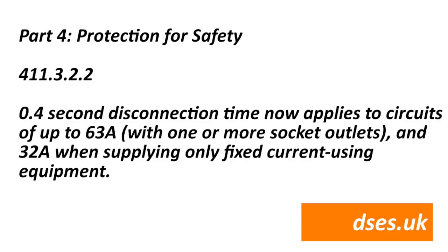Regulation 411.3.2.2 previously stated the maximum disconnection time for TN installations of up to 230V AC was 0.4 seconds for any circuit up to 32 amps, and 5 seconds for higher-rated distribution circuits. That has now changed slightly: 0.4 seconds now applies on circuits up to 63 amps with one or more socket outlets, and still 32 amps when supplying any fixed connected current-using equipment. Five seconds still applies to distribution circuits or circuits not covered by this regulation.